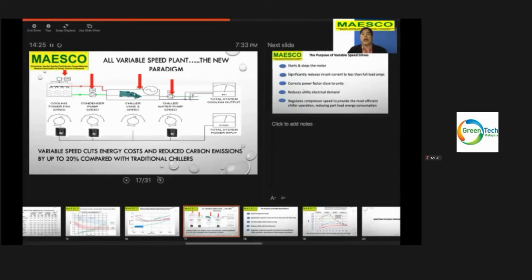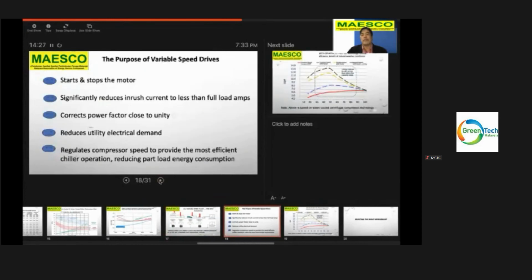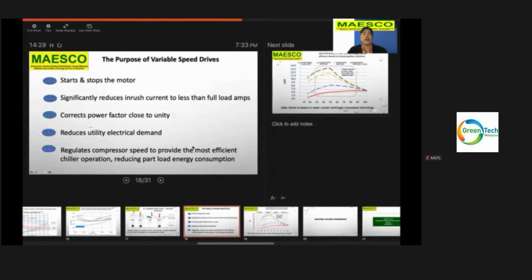Now, there are many other benefits of variable speed drive. It can be used to start and stop the motor, significantly reduces in-rush current to less than full load amps, corrects power factor close to unity, reduces utility electrical demand, regulates compressor speed to provide the most efficient chiller operation, reducing part load energy consumption.